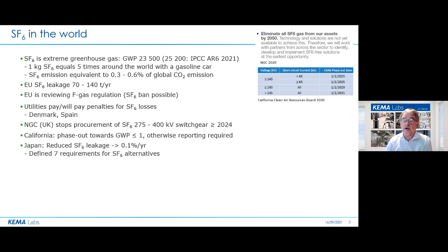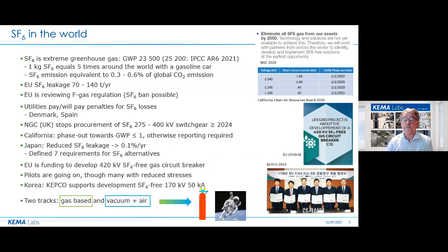The state of California in the US is embarking on a phase-out plan aiming at switchgear with a GWP of 1 at most. By 2031, all high voltage switchgear shall comply. Japan sets its cards on a stringent SF6 reduction. A remarkable 0.1% emission per year has been achieved, which is 5 times lower than the standards in IEC.